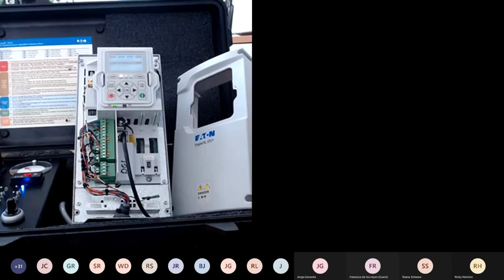You can see that this is not a three-phase VFD. I'm connecting this to my home outlet and I'm going through the live demonstration. So you can go through single to three-phase applications. Those are very neat solutions when you have 120 or 230 single. There are, however, some limitations. I believe the 120 volt to three-phase are very limited in horsepower range.